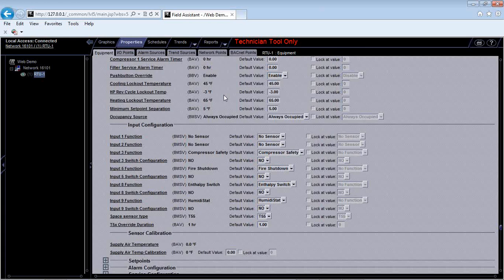This button is for if you have a space temperature sensor with a push button on it for overriding the schedule. Let's say that you have occupants who stay late and your schedule goes to 7 p.m., but they're in there at 9 p.m. and they're getting kind of cold. They would push this button on the sensor and you would go into occupied mode. On our controller, you can actually disable this function. So you can allow the end user, if he wants, to be able to push the button and think it comes on, but it won't. But that's purely up to you as to if you want to give them that option or not.